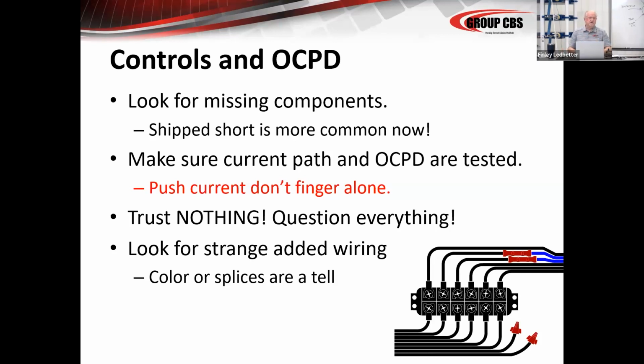During COVID, for instance, a lot of equipment was built with casual labor instead of their normal wiremen. So be careful of that equipment that's out there that's coming into service right about now. Reliability is a sense of safety and a sense of calm. And what we're trying to do is express the fact that we want the equipment to be reliable between maintenance cycles, not just one day, the day you test it. To do that, you have to have a base starting point that's reliable. And that's what we're talking about for people that come in late.